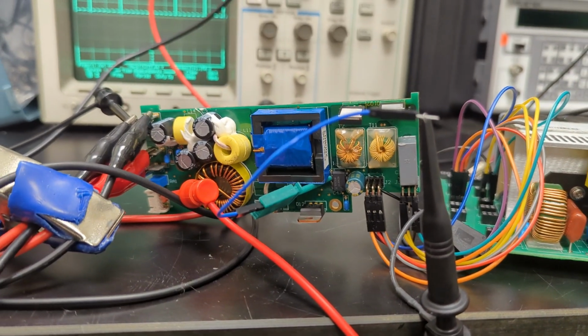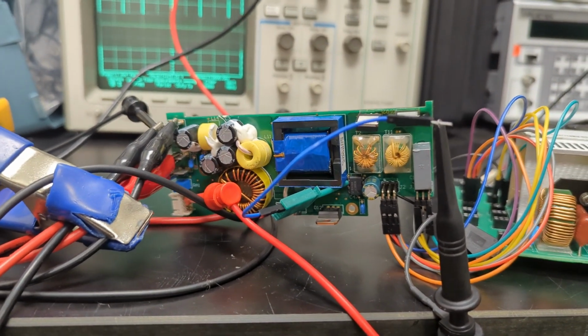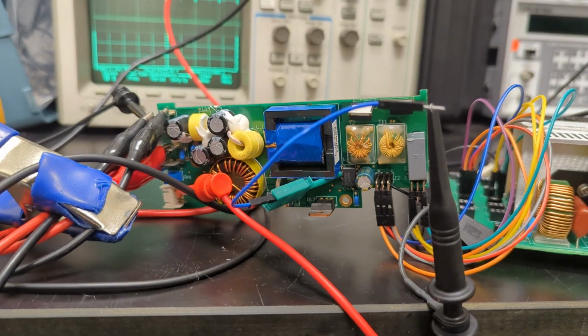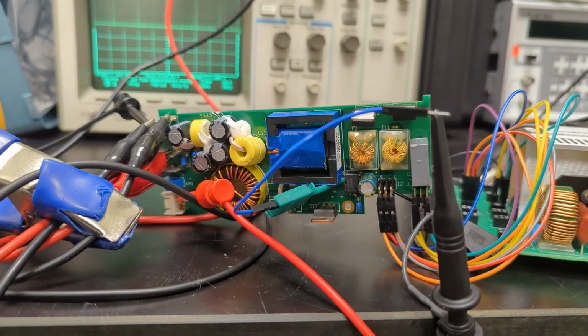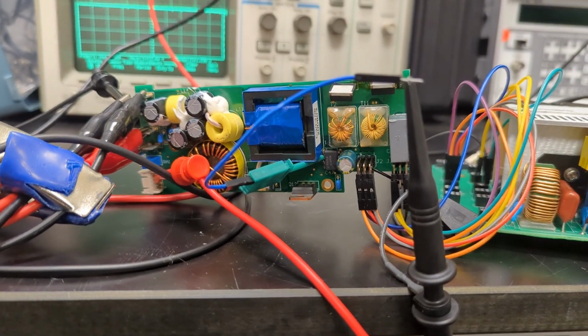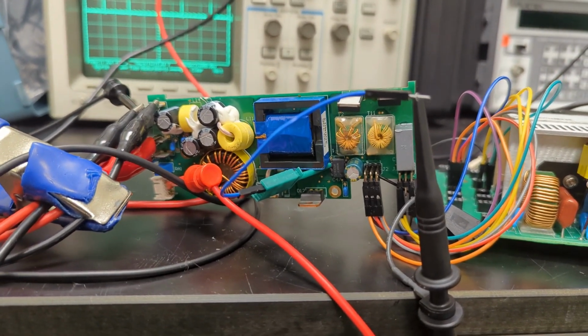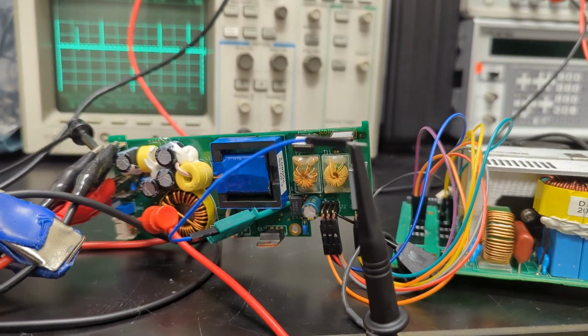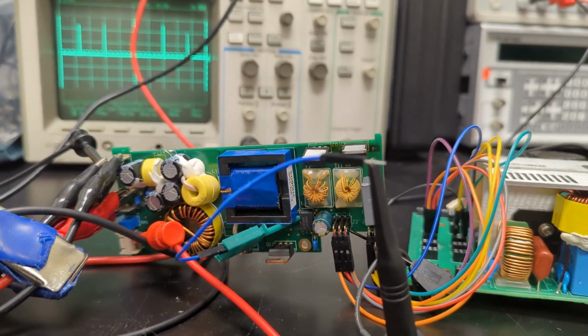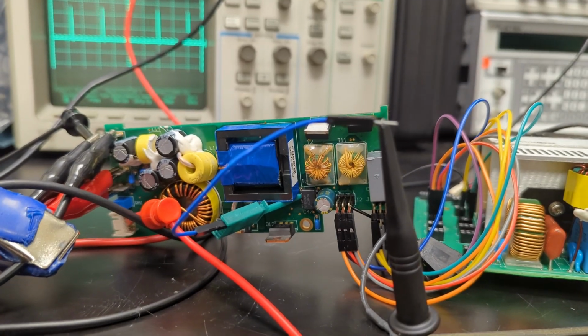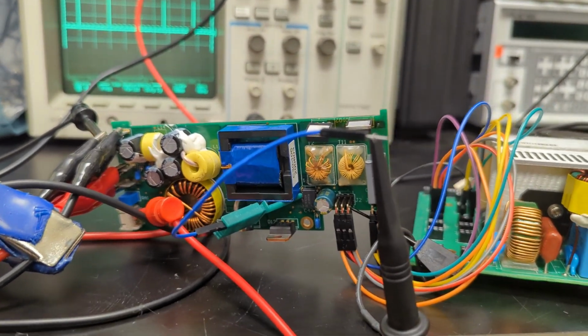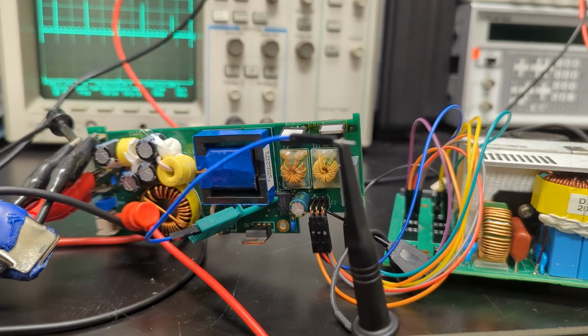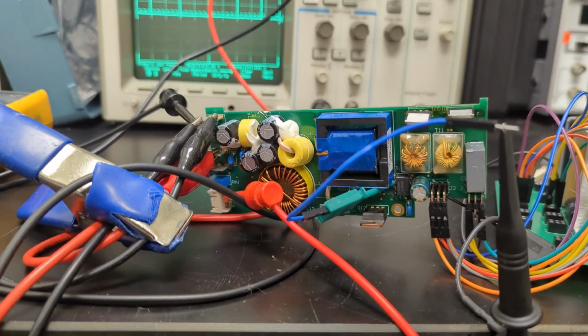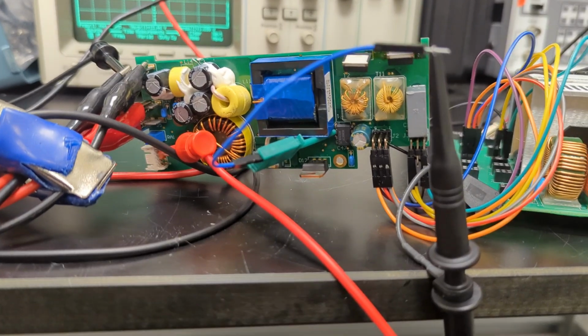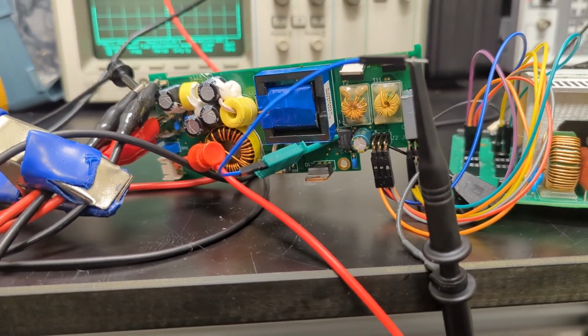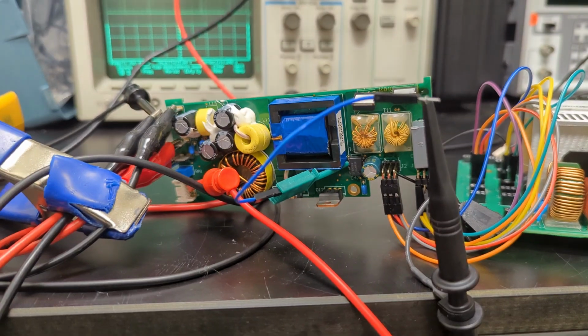That actually happened on the 24 volt module. I'm not 100% sure, I can check the monitoring system again on the centrifuge, but that one doesn't get nearly as high as far as power output, and yet that's the one where SMD components had literally fallen off the board. So I think it's a combination of two things: poor heat dissipation on the supply end, and the manufacturer of the centrifuge not picking a suitable supply.